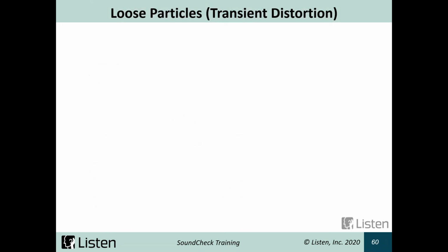Loose particles is available with every algorithm type. So if we're using Harmonictrak, heterodyne, TSR, RTA, doesn't matter what we're doing, we can enable loose particles and set that to catch any loose particles in our device.